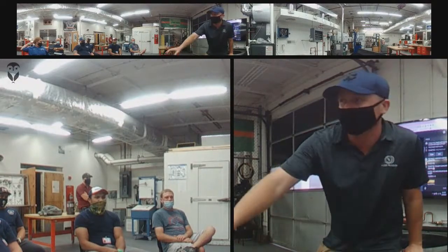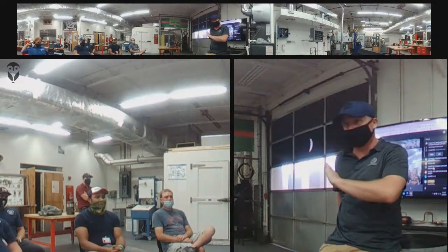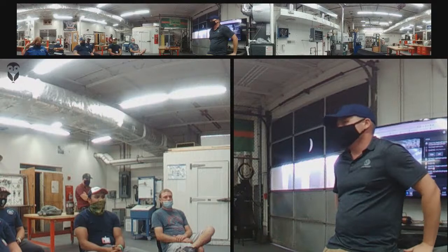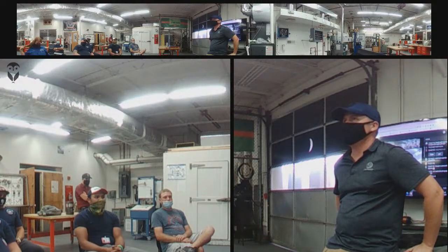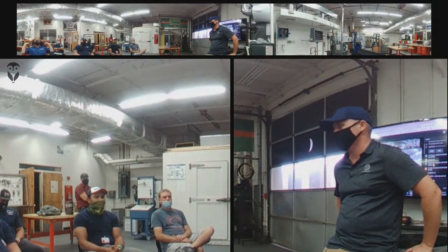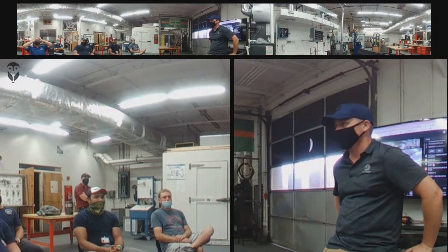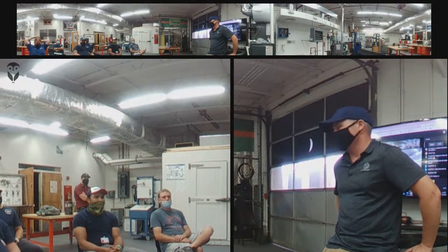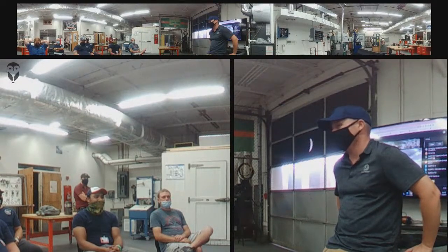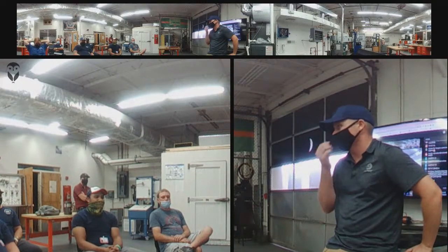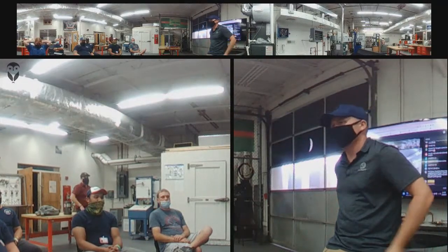Now, one thing to note, just a good thing to know, if you've ever got issues with large condensers where a condenser fan motor or maybe even corrosion is causing a high head event that is temporary or you're waiting on parts, you can take a sprinkler and put it on it. Yeah, I did. I got a hose. You got a hose, okay. Yeah, and that will do as good of a job, if not better in some cases, than a condenser fan motor. Now, you don't want to run that.